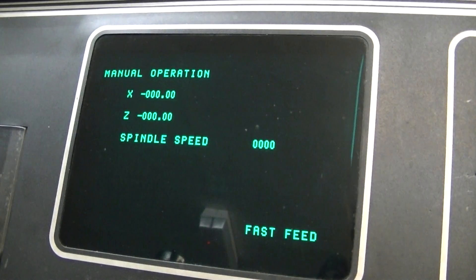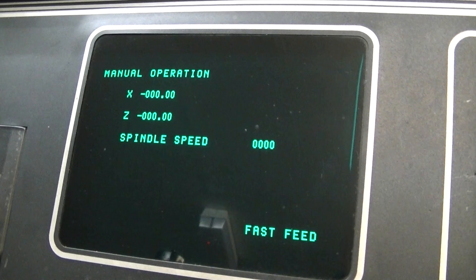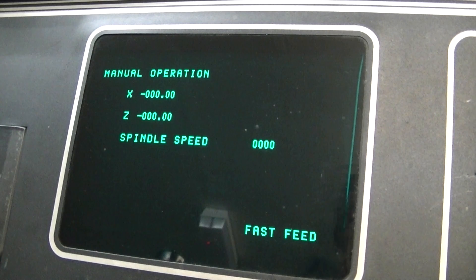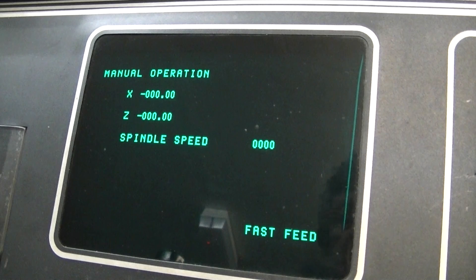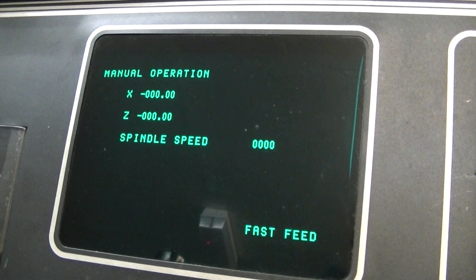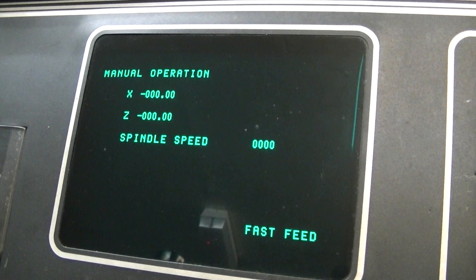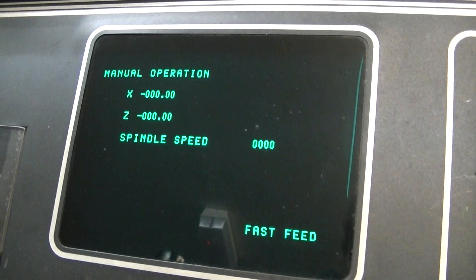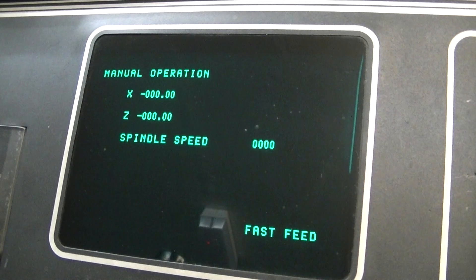It goes to the manual operation screen. The important thing to watch here for is that X and Z are at the same position as the datum is set in the program. In this case they are, which is X is 0, Z is 0.